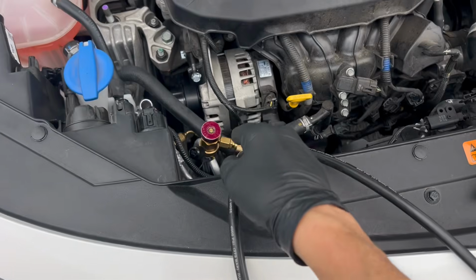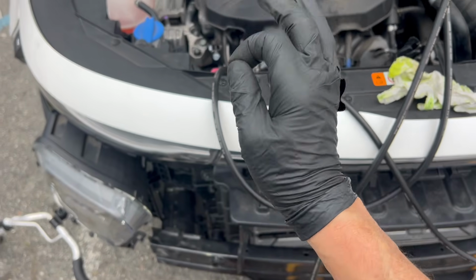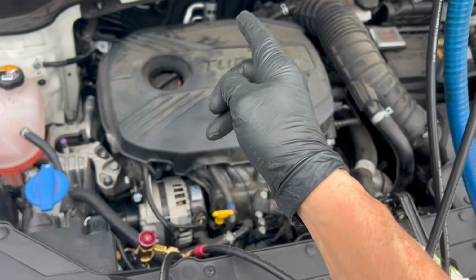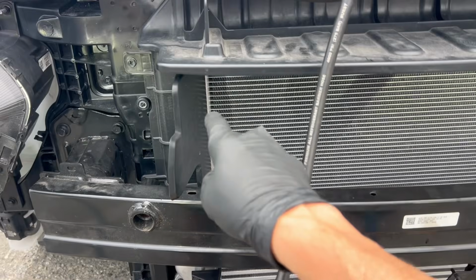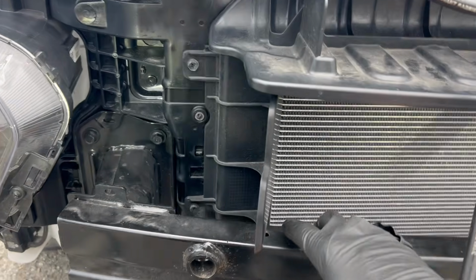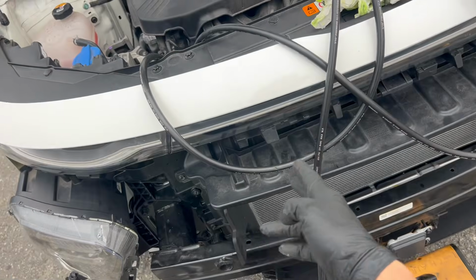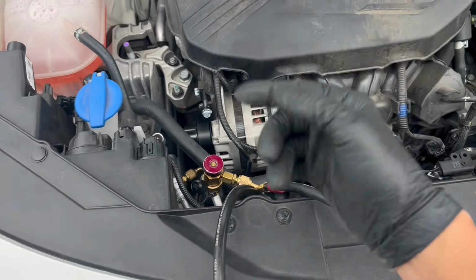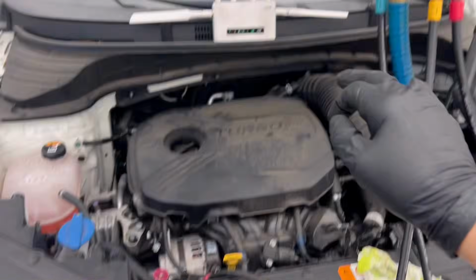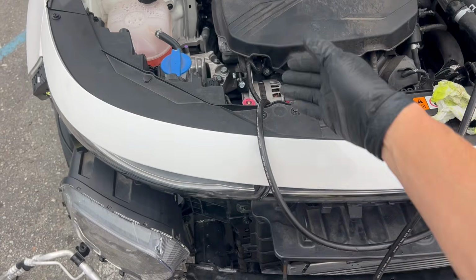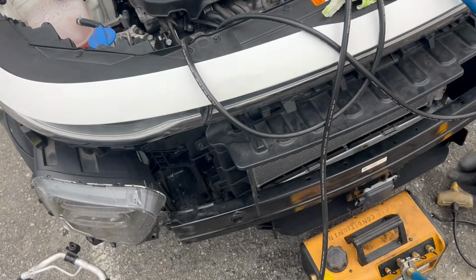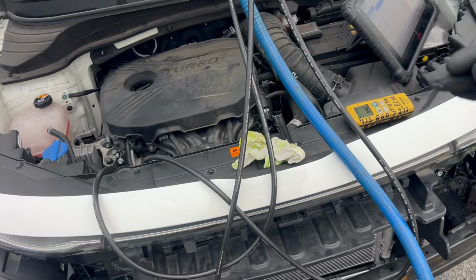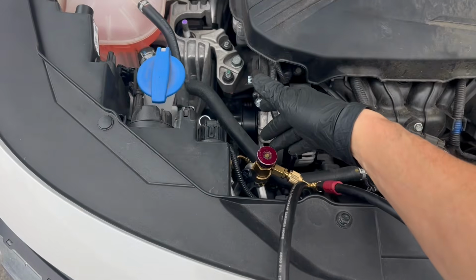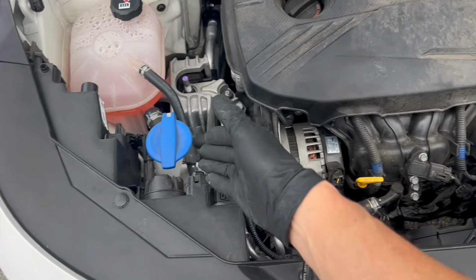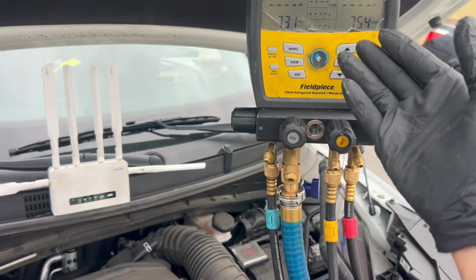If you want to know if your compressor was starting to come apart, it didn't come apart all the way. It made some metal flakes. It's still making pressure and it's still working, but it's not working good. But it puts some metal debris inside the small tubes of the microchannel. Well, how will that show up? You can have either low airflow or debris backing up the refrigerant, causing a high side, and you'll read here 400 psi. But when you look at your Autel and you look at the pressure transducer, say you have 88 psi. Well, how can you have 400 psi here and 88 psi at the other side of the condenser? You have a restriction, and you can prove that because you had two points of measurement for pressure, one before and one after. One was by the pressure transducer, you used your Autel. The other one was your gauges.